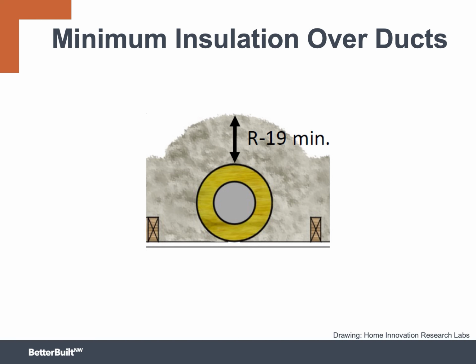To meet Oregon code, a minimum of R19 insulation must be placed over the top of the ducts. The insulation depth will vary depending on the R value of the specific material that you're installing. Here's an example. Typical blown fiberglass has an insulating value of R2.7 per inch, so there would need to be 7 inches of fiberglass over the duct. Spray foam insulation can be used too. The thickness of the foam needed to reach R19 depends on the specific product being used.